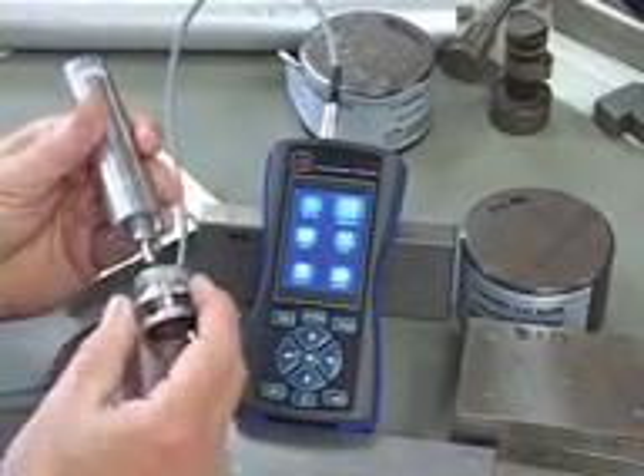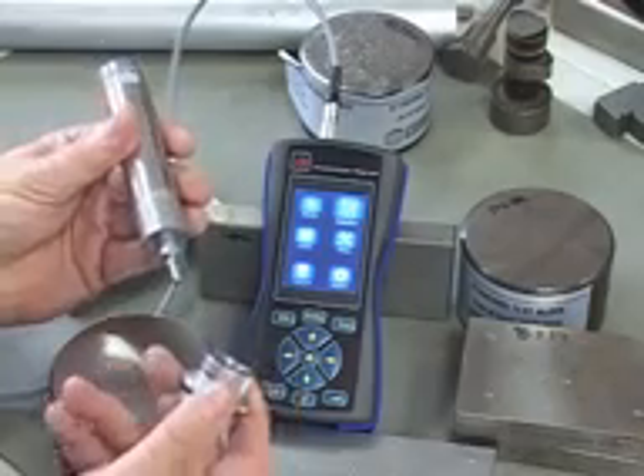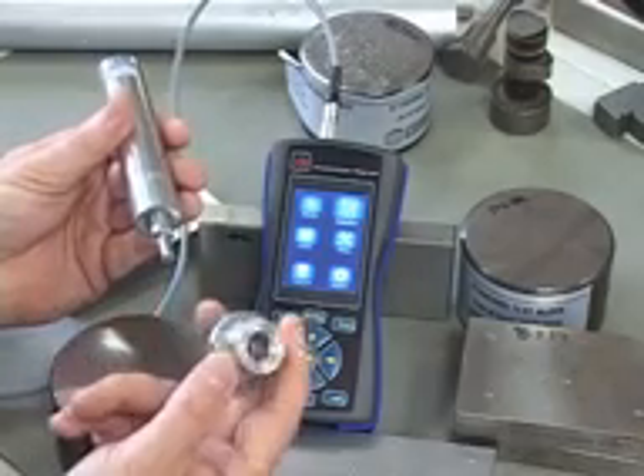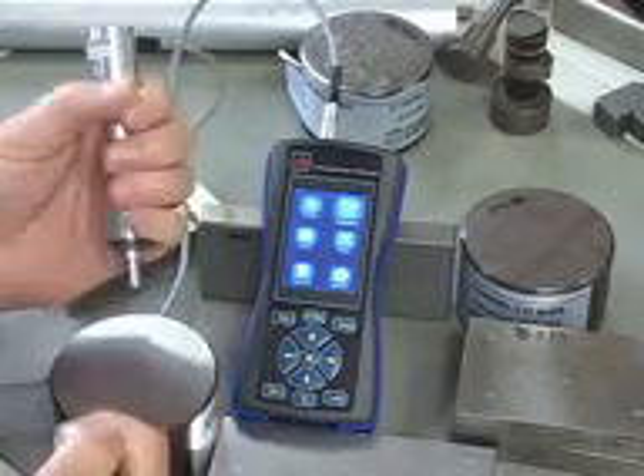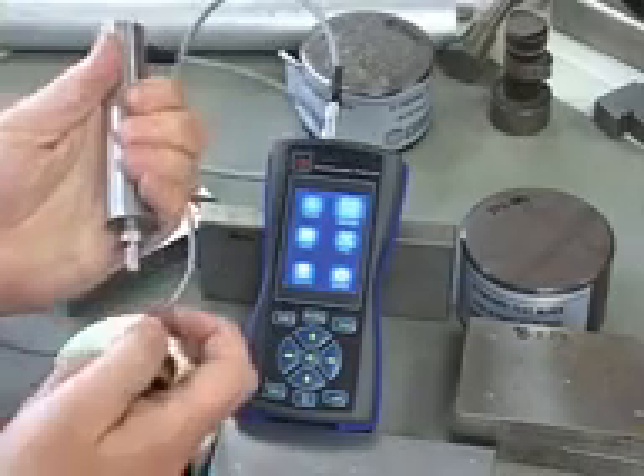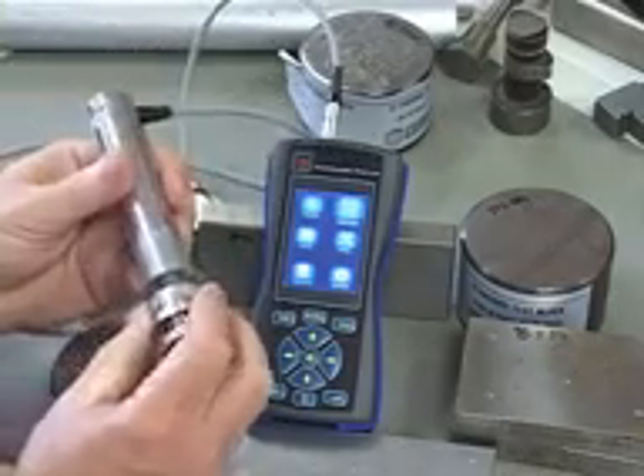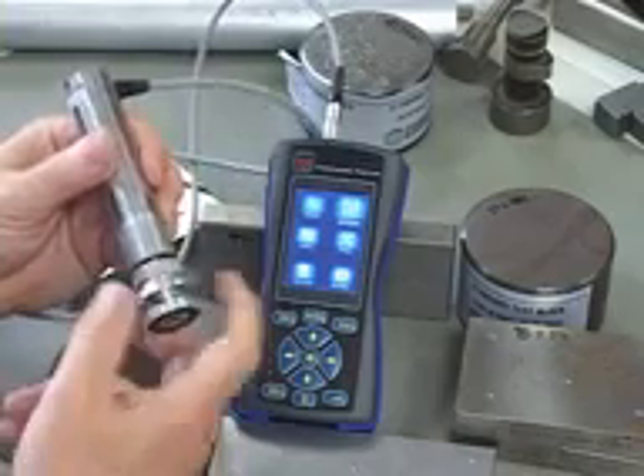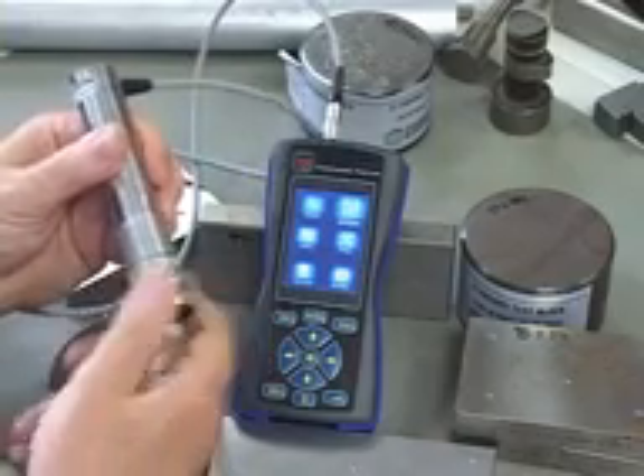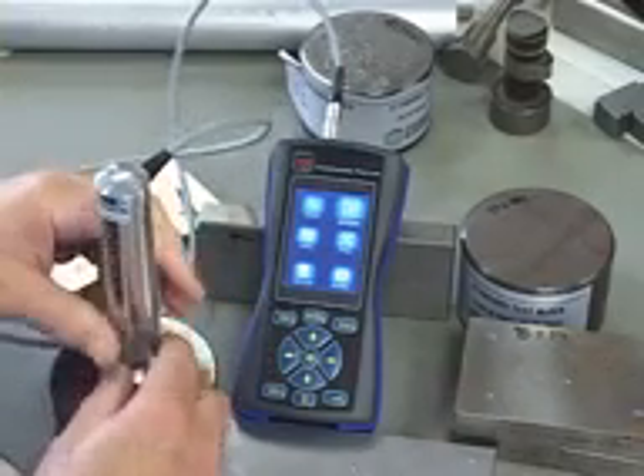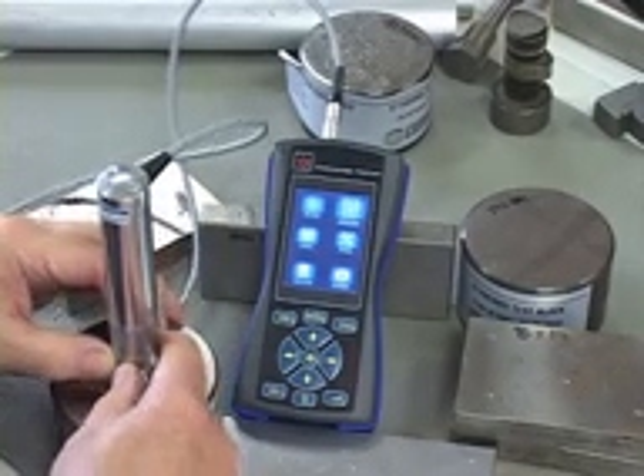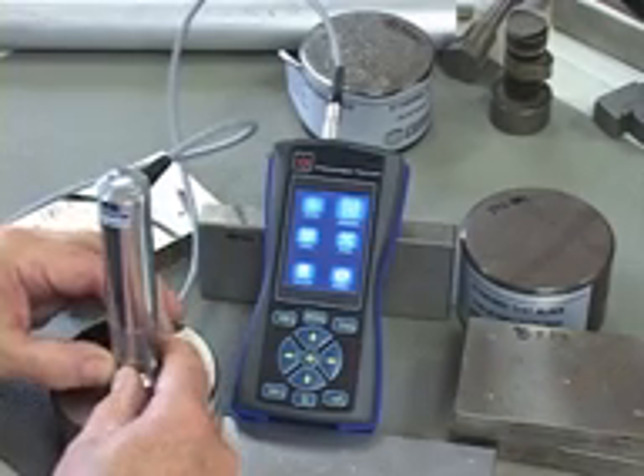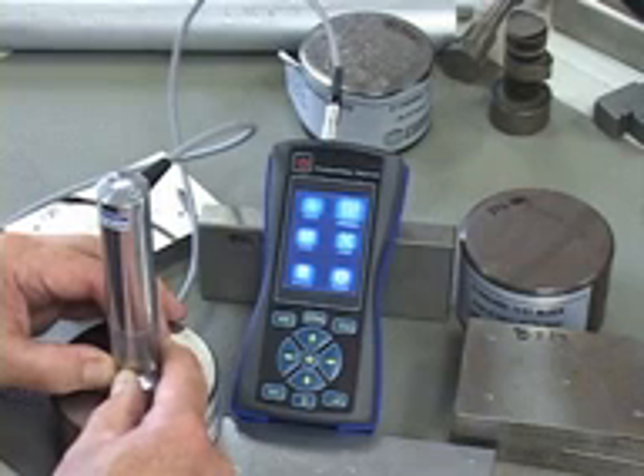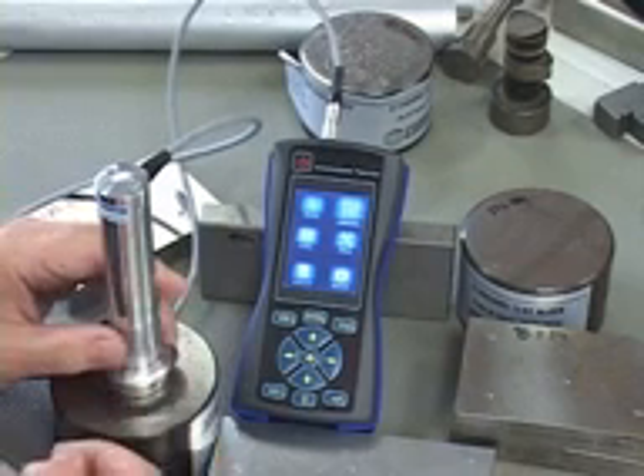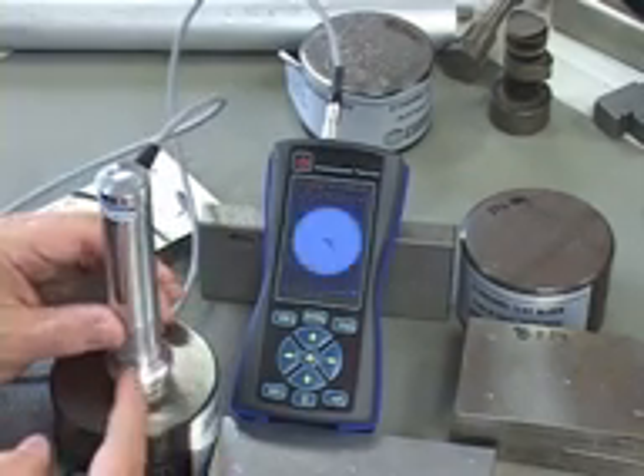So when this is screwed on, and you can leave it off for a more experienced user, you can use it without this puck and just use the device like this for doing testing. But for a new user, it's much easier to use it with the puck attached.